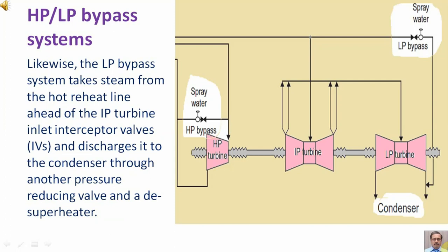Likewise, the LP bypass system takes steam from the hot reheat line ahead of the IP turbine inlet interceptor valve and discharges it to the condenser through another pressure reducing valve and a desuperheater.